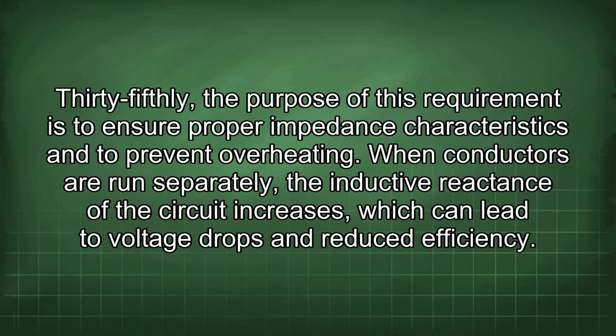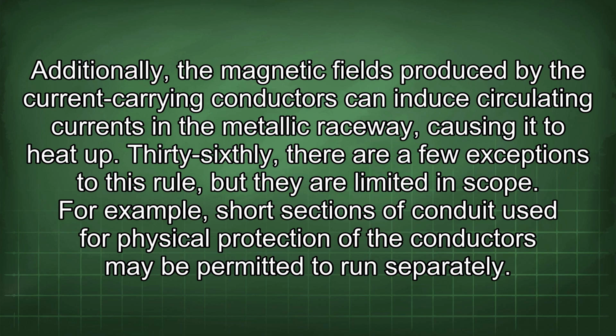35thly, the purpose of this requirement is to ensure proper impedance characteristics and to prevent overheating. When conductors are run separately, the inductive reactance of the circuit increases, which can lead to voltage drops and reduced efficiency. Additionally, the magnetic fields produced by the current-carrying conductors can induce circulating currents in the metallic raceway, causing it to heat up. 36thly, there are a few exceptions to this rule, but they are limited in scope.